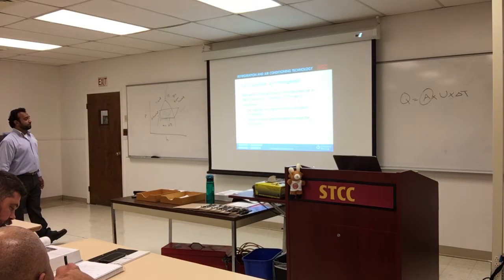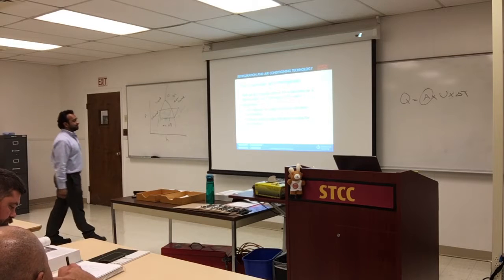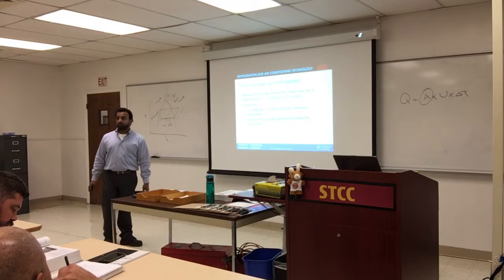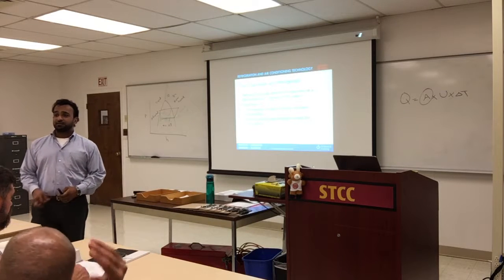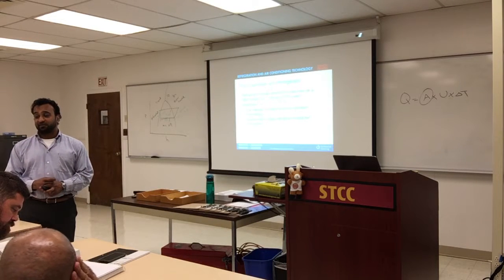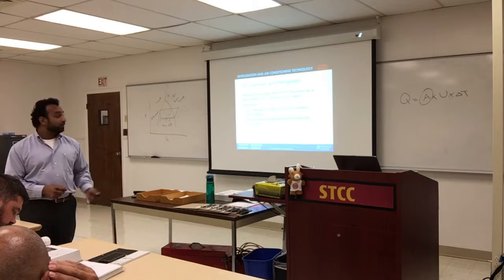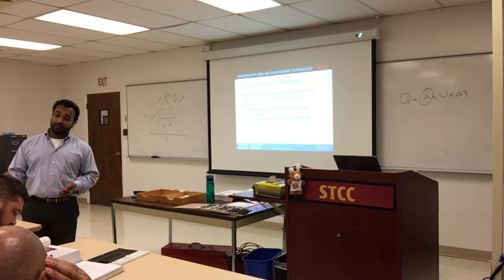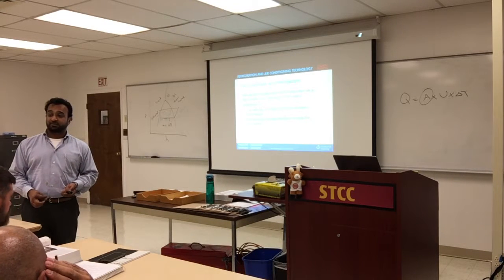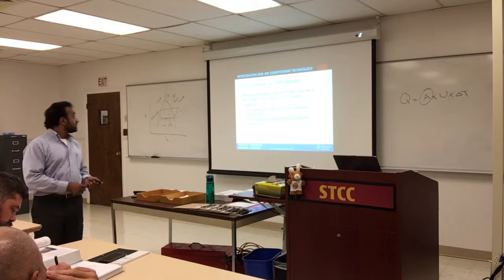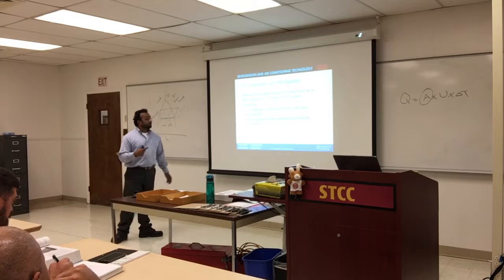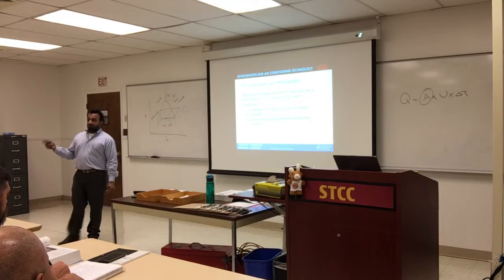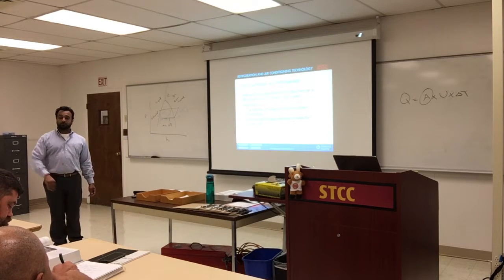Also the evaporator ensures that no liquid refrigerant enters the compressor, which makes sense because the compressor does not deal with liquid, it will break or malfunction. That's why we are going to have superheated vapor going into the compressor. No liquid should go in there. So when we go to that diagram, coming from the evaporator, it's always going to be superheated.